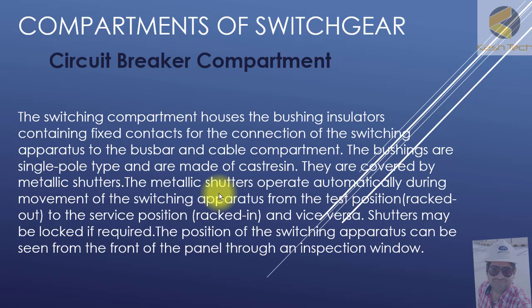The metallic shutters operate automatically during movement of switching apparatus from the test position, rack-out, to the service position — that's called rack-in — and vice versa. Shutters may be locked if required. The position of switching apparatus can be seen from the front of the panel through an inspection window.